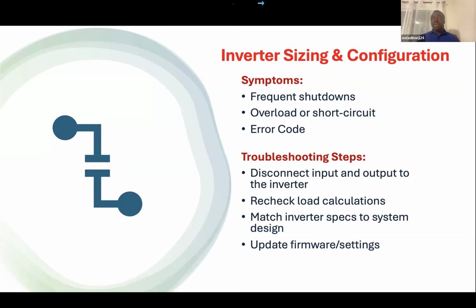For frequent shutdowns, so many things can be responsible. Overload: the best way to troubleshoot overload is that most smart inverters these days will tell you there's an overload, or show you some error codes or short circuits. In the case of short circuits, you just see that the inverter is tripping off frequently. You will power up again and trip off again. So the best way to troubleshoot systems like this is to first isolate the input and the output. Try to run the inverter on battery only and see if, after disconnecting the input and the output, the inverter is able to run seamlessly for maybe 5 minutes.